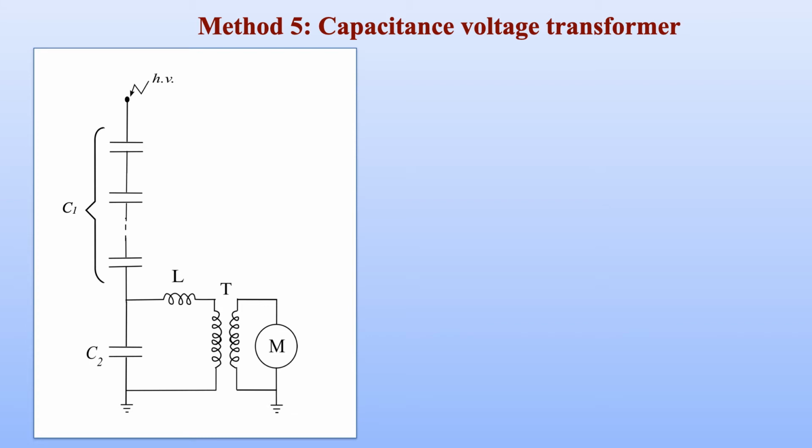We can clearly realize that even though the capacitance potential divider method overcomes some of the limitations of series capacitance and series resistance methods, it still has some stray capacitances, and special capacitor construction is required. The gas compressed capacitor is used, right?